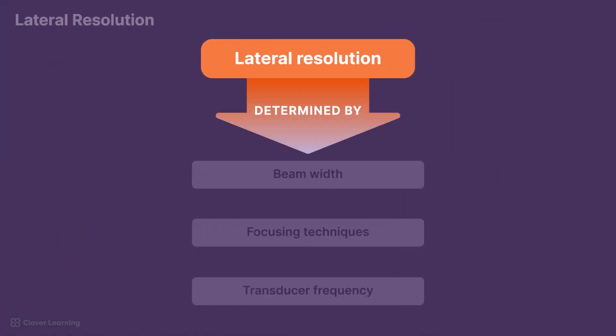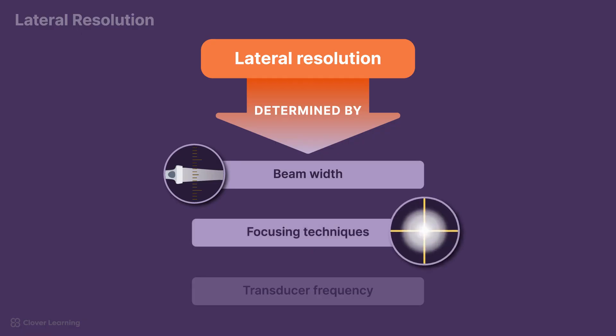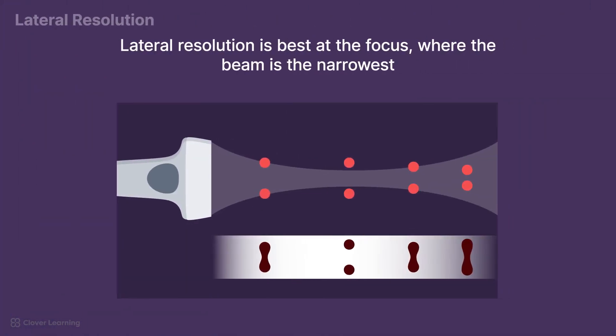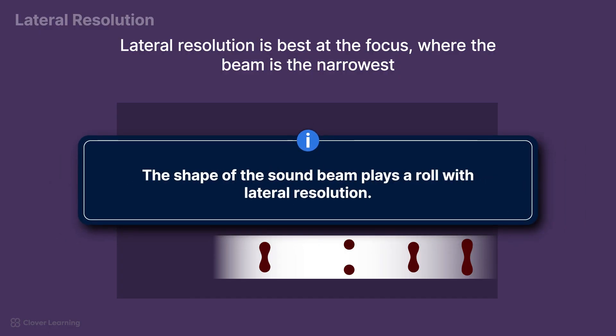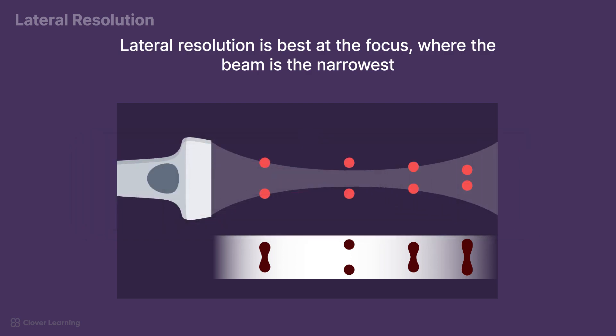Lateral resolution is determined by beam width, focusing techniques, and transducer frequency. A narrower beam provides better lateral resolution by minimizing the overlap of adjacent echoes. As a reminder, the shape of the sound beam plays a role with lateral resolution, which is discussed more in another lesson. Ultrasound systems use electronic or mechanical focusing to narrow the beam width at specific depths, which enhances lateral resolution in the focal zone.